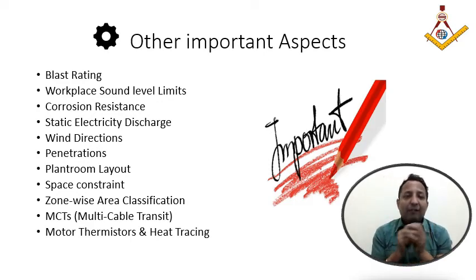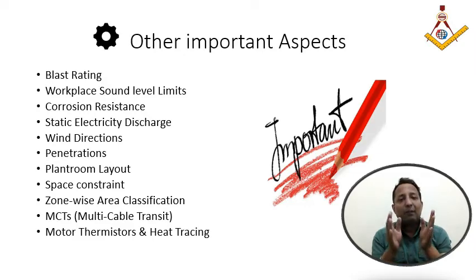When the study is concluded and the technical safety department says that due to the blast there is a danger to accommodation, then wherever there are openings for either fresh air or exhaust, it is recommended to provide blast rated walls or blast rated dampers. If you Google it, you will understand what I mean.